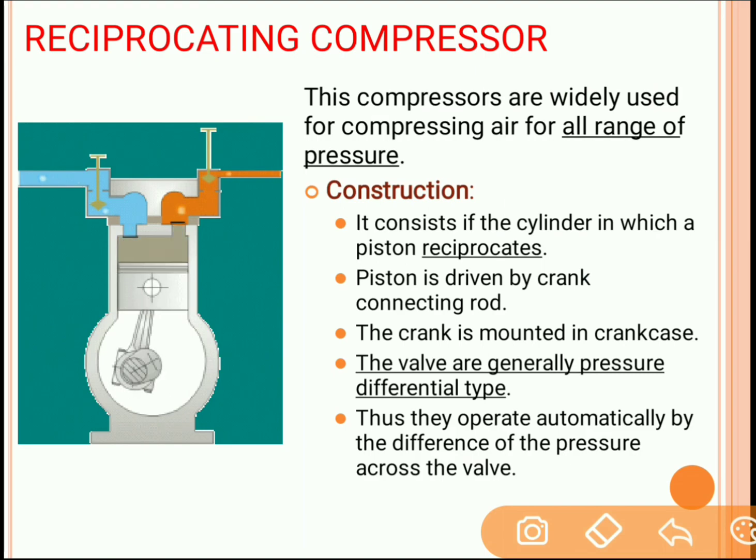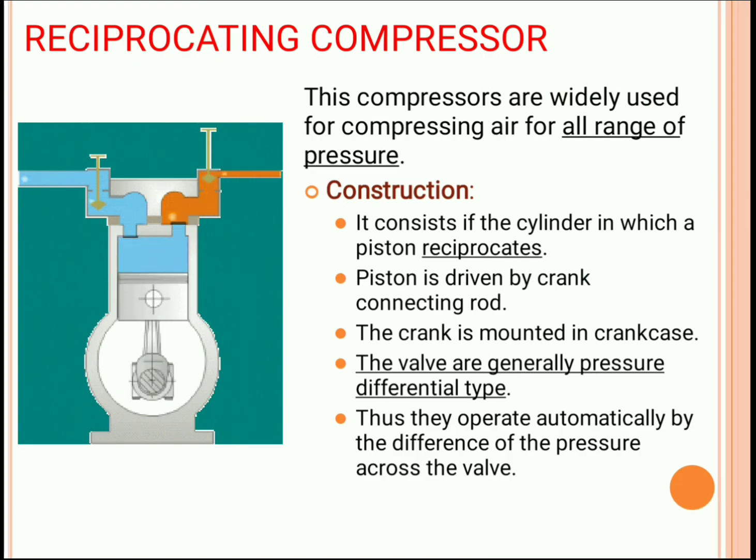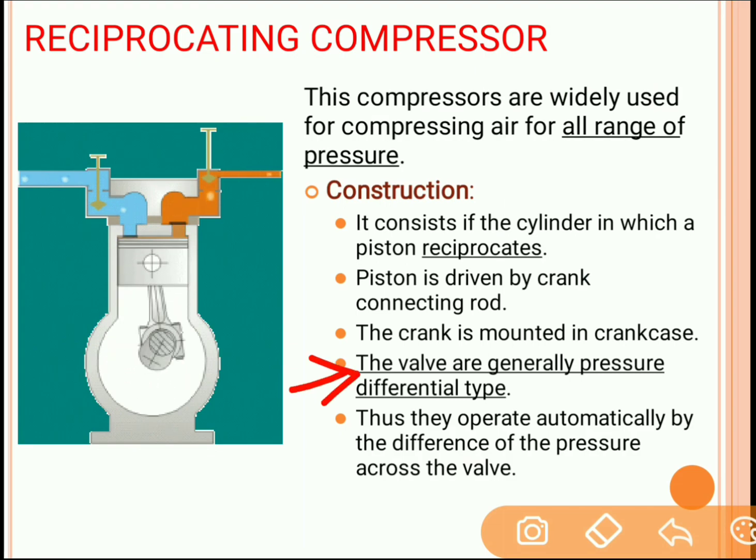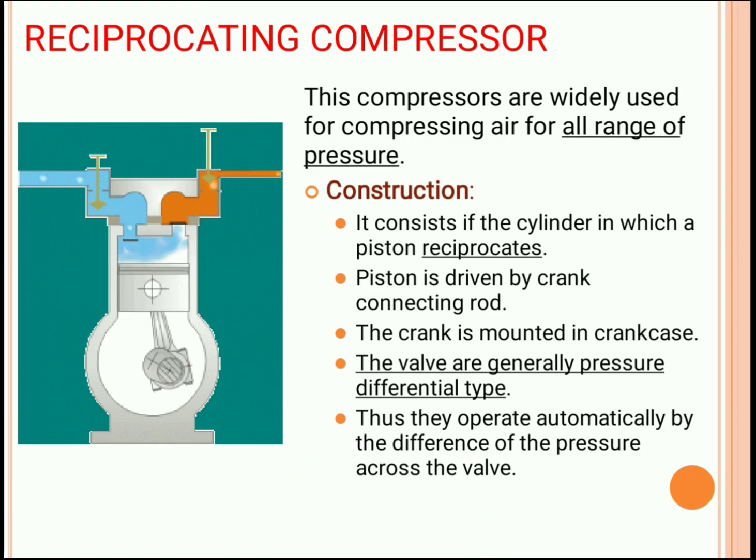And when the piston moves in the upward direction, the air which is already inside the cylinder will get compressed. So the pressure of the air will increase, and the pressurized air will now transfer to the delivery pipe. The suction valve and the delivery valve are pressure differential type. Thus, they are operated automatically by the difference of pressure across the valve.